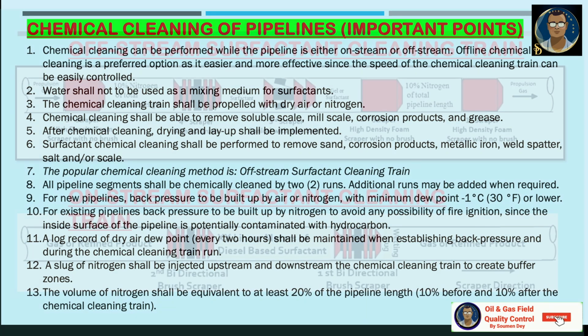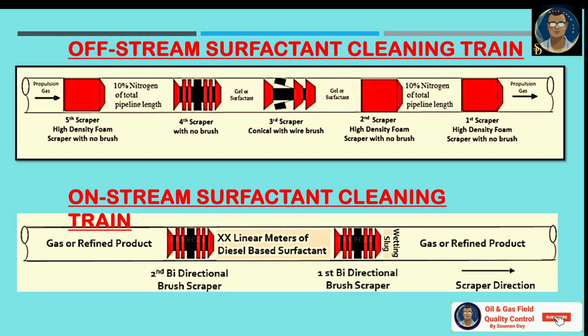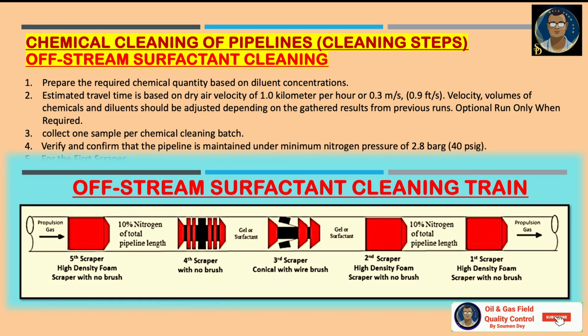Before is to create the back pressure and 10% after to give the drive force to the chemical cleaning train. You can see the arrangement of the off-stream surfactant cleaning train and an arrangement of the on-stream surfactant cleaning train. Now we will discuss the cleaning steps for off-stream surfactant cleaning, because this is the most popular one we are using at the pre-commissioning stage basically. Prepare the required chemical quantity based on diluent concentration. Then the estimated travel time is based on the dry air velocity of 1 km per hour or 0.3 meter per second, which is converted to 0.9 feet per second. Volumes of chemicals and diluent should be adjusted depending on the results gathered from previous runs. Optional run only when required.